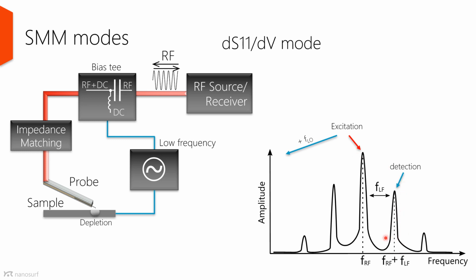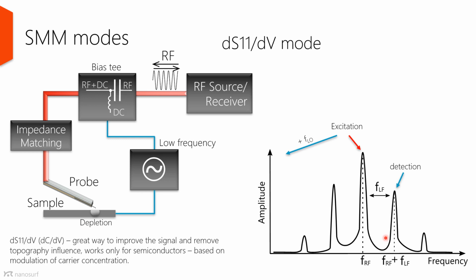So the source and the receiver are not working on the same frequency anymore. So this would be the so-called dS11/dV mode, and it is very close to the dC-dV mode from the scanning capacitance technique. This mode works only for semiconductors, and it is not affected by the topography as the standard S11 measurement is. There could be different technical realizations of this mode. For example, using a mixer and mixing the product signal back down to DC, and using a lock-in amplifier working on the frequency of the low frequency modulation. But a better way is to set your detector to work directly on the sideband frequency and directly measure the RF signal strength here. This way is preferable because you would be much further away from 1/f noise.